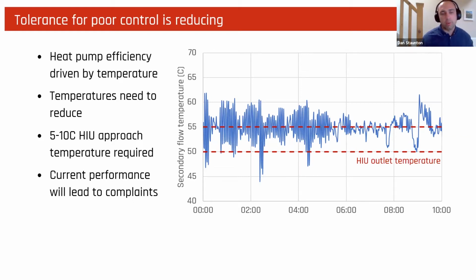If we overlay, like we have done on the right-hand side here, the current levels of stability that we see, and I should say this is a fairly common level of stability, we haven't picked out a particularly poor plate heat exchanger, you'll see that if we're trying to maintain a 5 degree approach temperature, we can't do that. So our current approach, our current designs, our current controls don't provide adequate stability for us to maintain comfort, domestic hot water and space heating continuously.